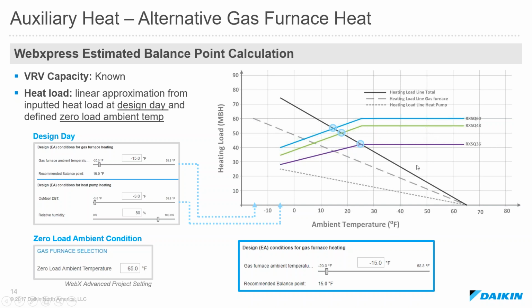And you'll see as the system gets larger, that intersection point shifts to the left. So you're switching over at a later point in time. And that makes sense, right? Because you have more capacity on that system. You're not going to run out of heating capacity until it gets a little bit colder outside. And then if you're familiar with WebExpress, the conditions for the gas furnace are going to be present on the selection of the A coil, and this will also be present on the outdoor unit properties pane. So it's going to be labeled as a recommended balance point, and in this case you see with a 5-ton unit it's 15.